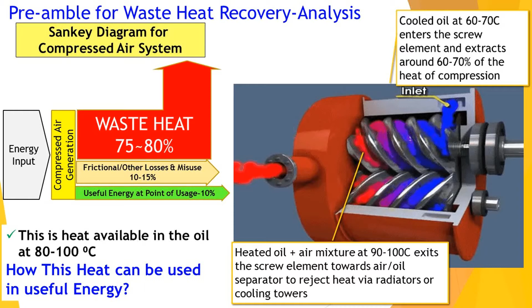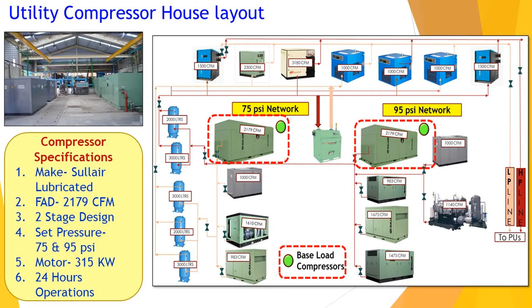This is our compressor house. We have two streams of compressed air systems, 75 psi and 95 psi, and two sets of compressors. We identified two baseload compressors, two-stage lubricated ones with FAD 2179 CFM and a 315 kilowatt motor. This is the air-oil circuit of the compressor: at the discharge end, air and oil are compressed and sent at 95 degrees. There is an air-oil separator where air is separated out and the oil returns through a water-cooled oil cooler, gets cooled, and is recycled again. The flow rate is about 280 to 300 liters per minute.